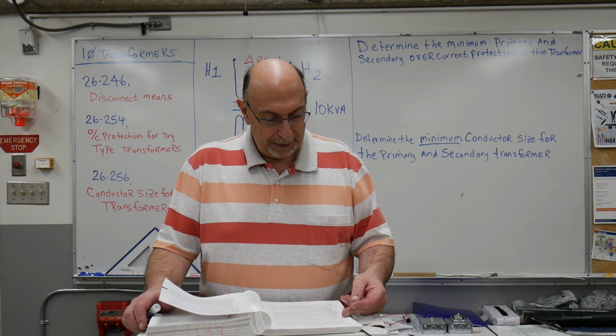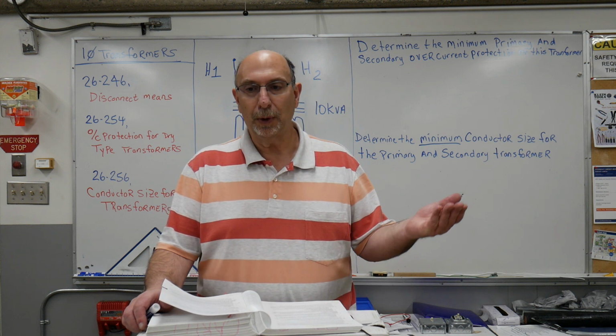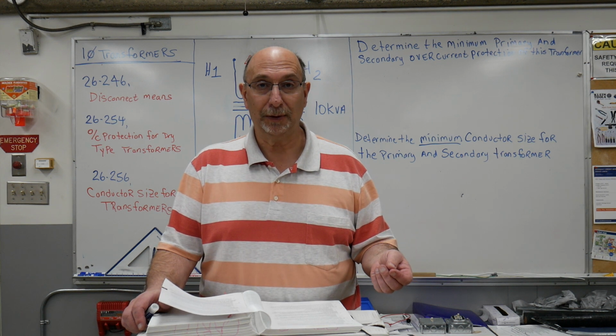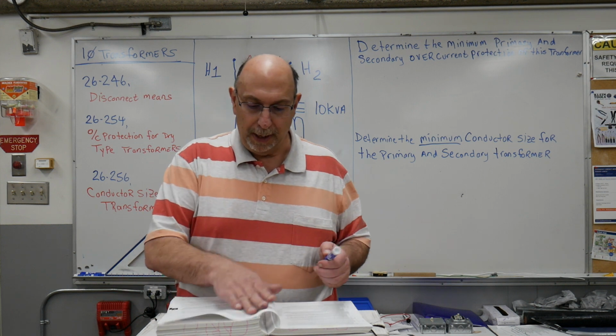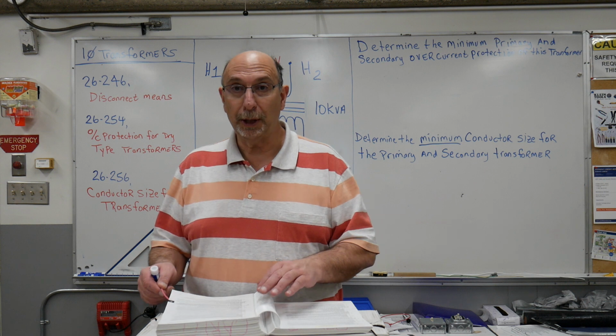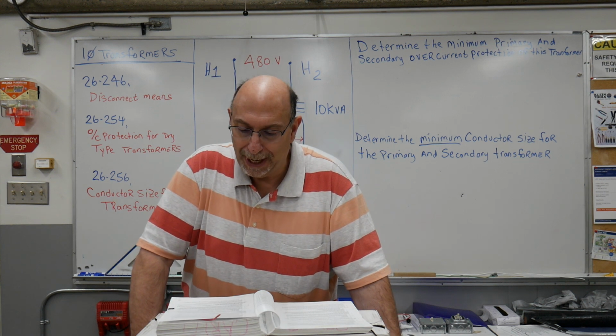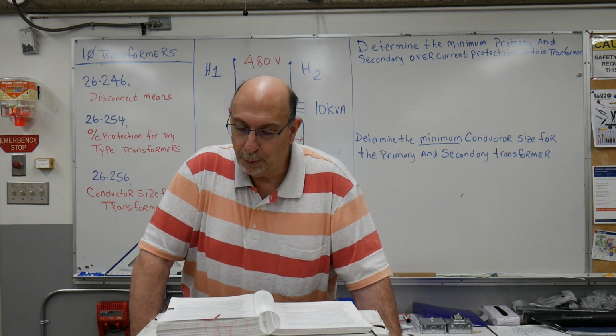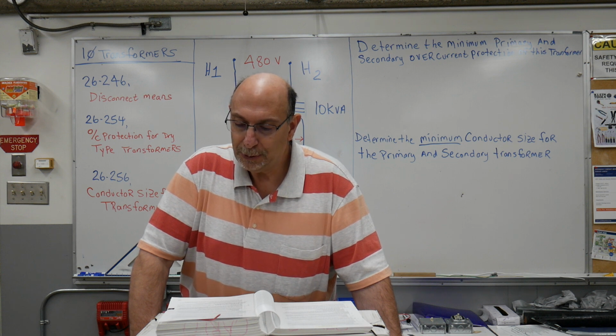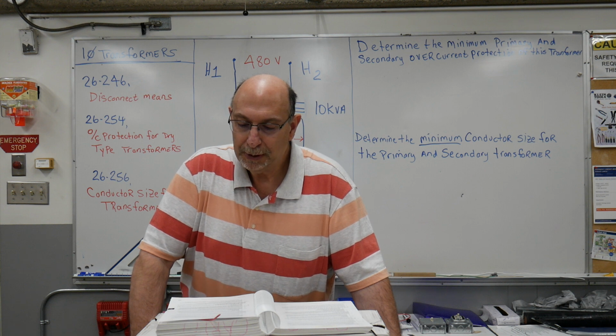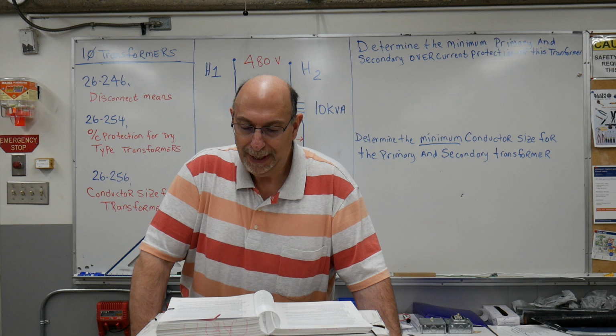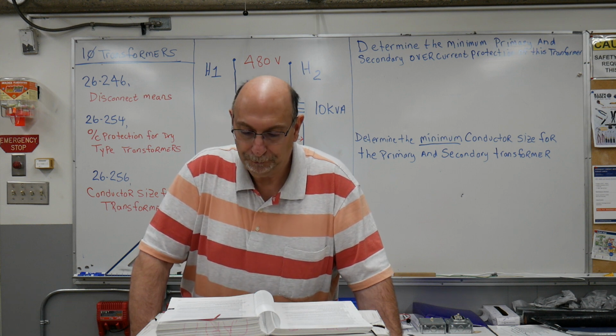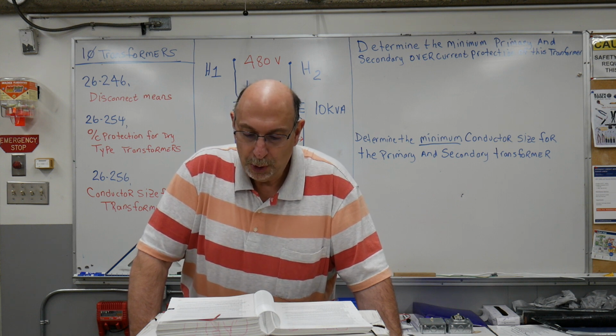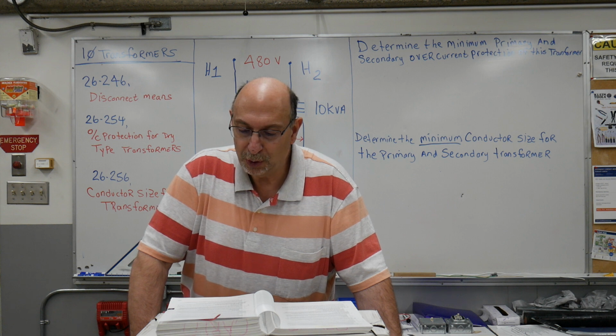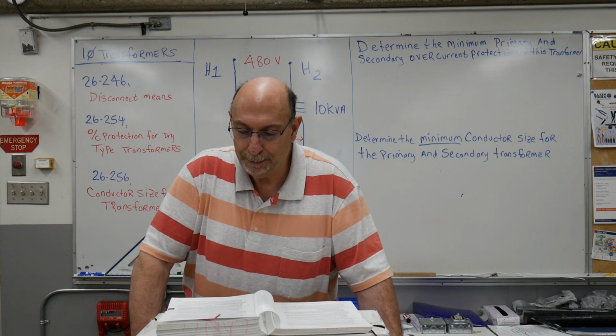All right, we're not going to talk about 26-242, outdoor transformers and unit subs, because we're just dealing with dry core, open ventilated transformers. Just the basics. One thing I forgot to mention to you when we were upstairs at the third year lab: for dry core transformers, especially 26-246, which we're dealing with, the open ventilated type shall be mounted so that there is airspace of not less than 150 millimeters between the transformer enclosure and any adjacent surface, except floors. Notwithstanding subrule 1, where the adjacent surface is a combustible material, the minimum permissible separation between the transformer enclosure and the adjacent surface shall be 300 millimeters.